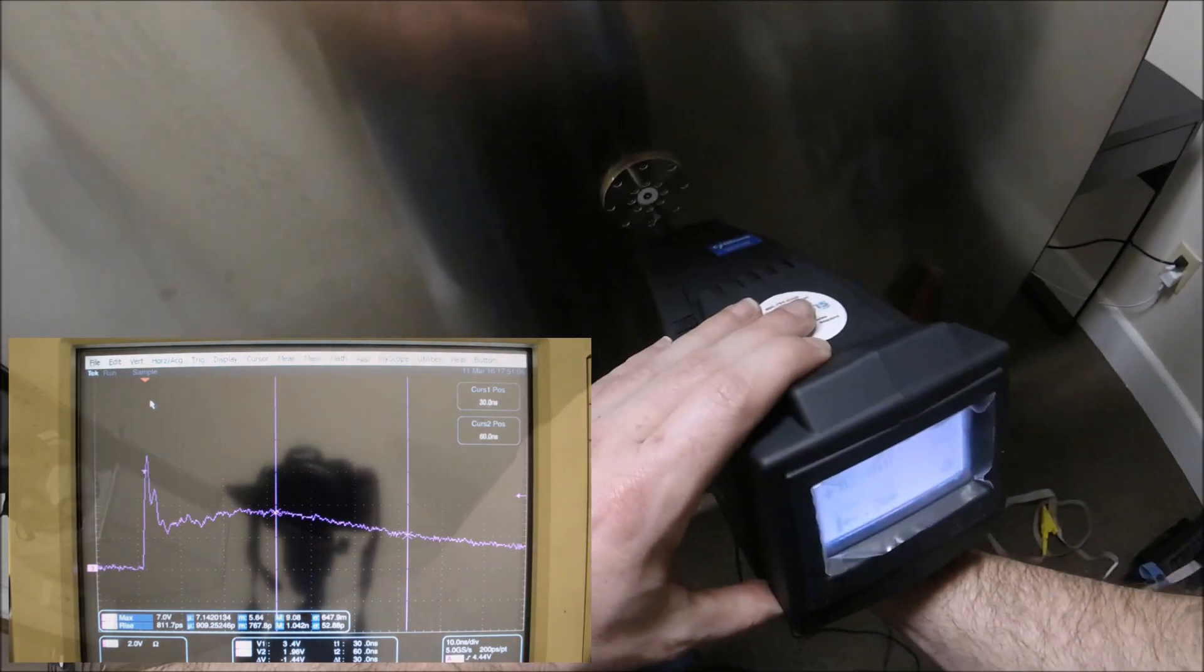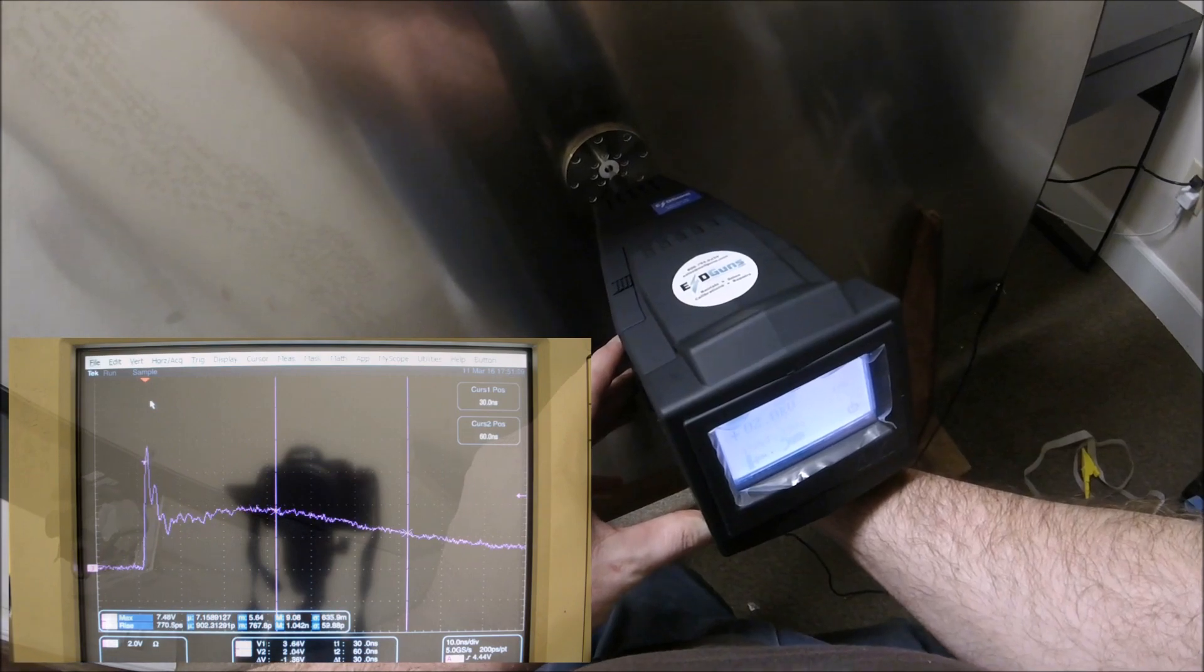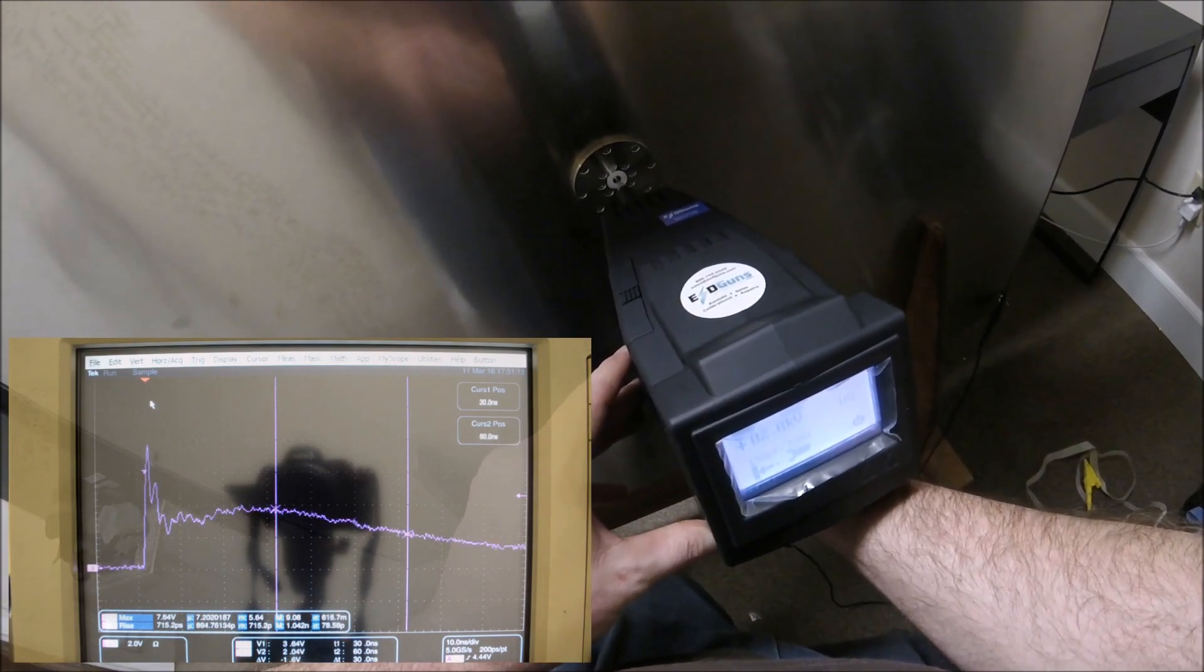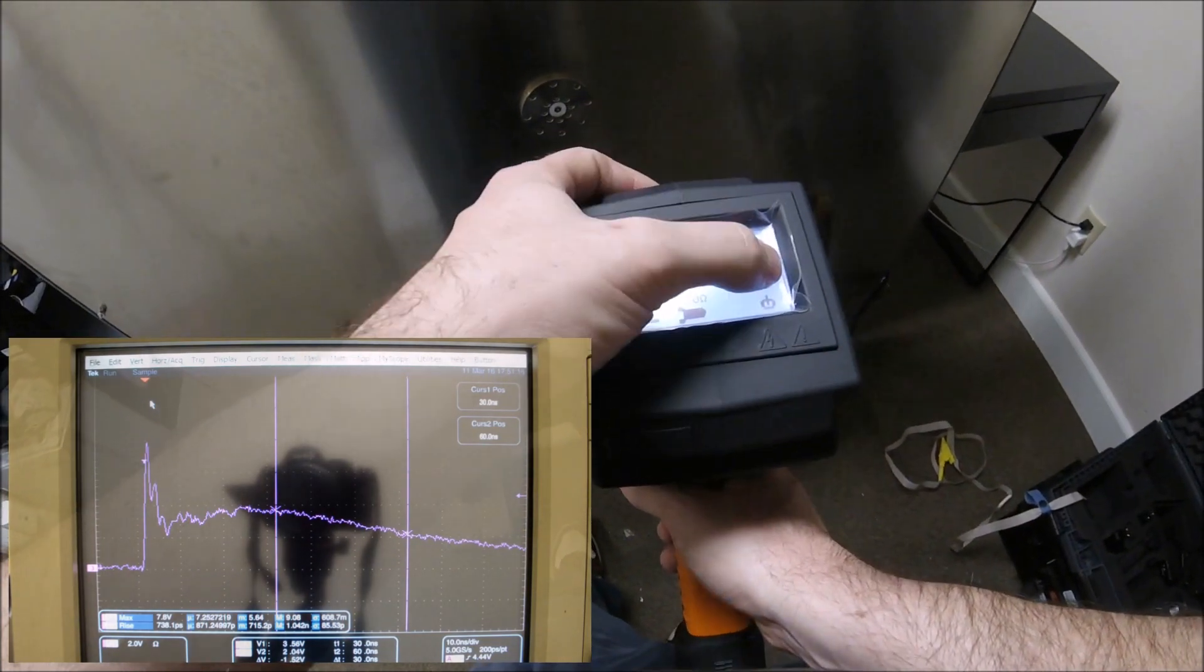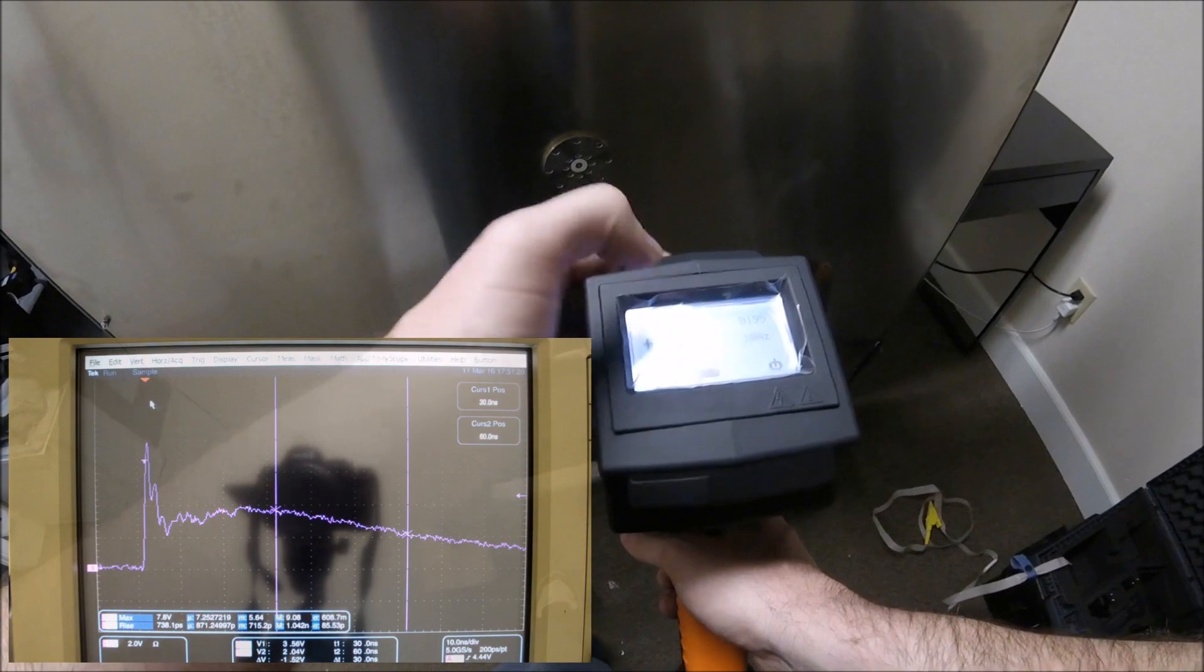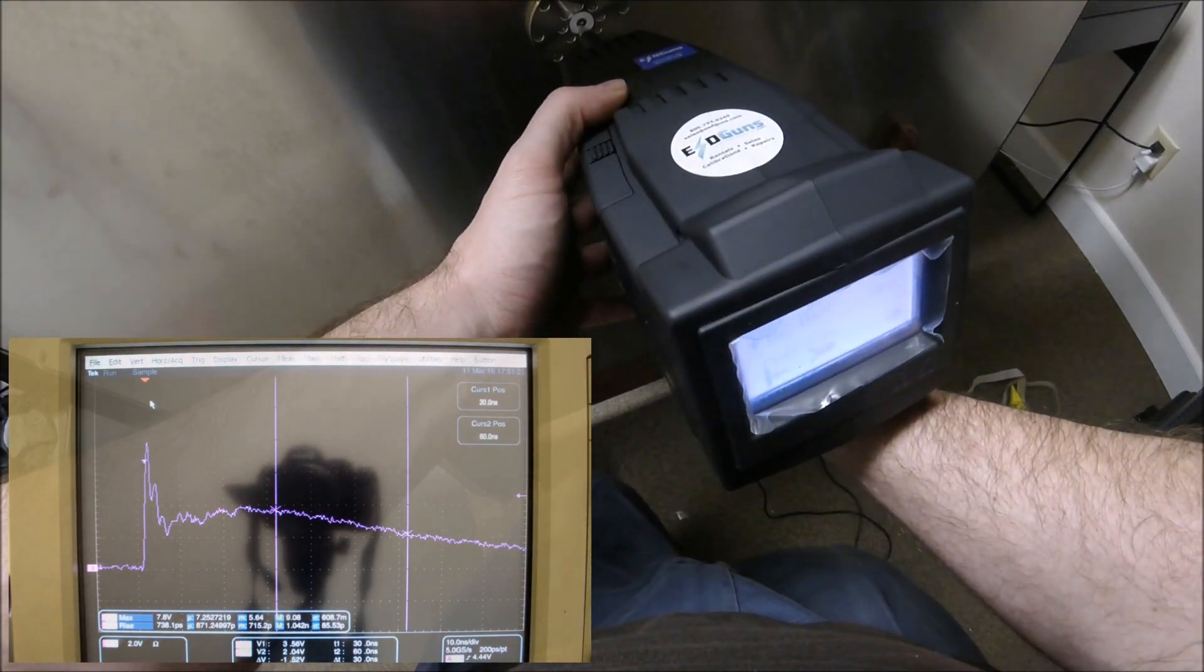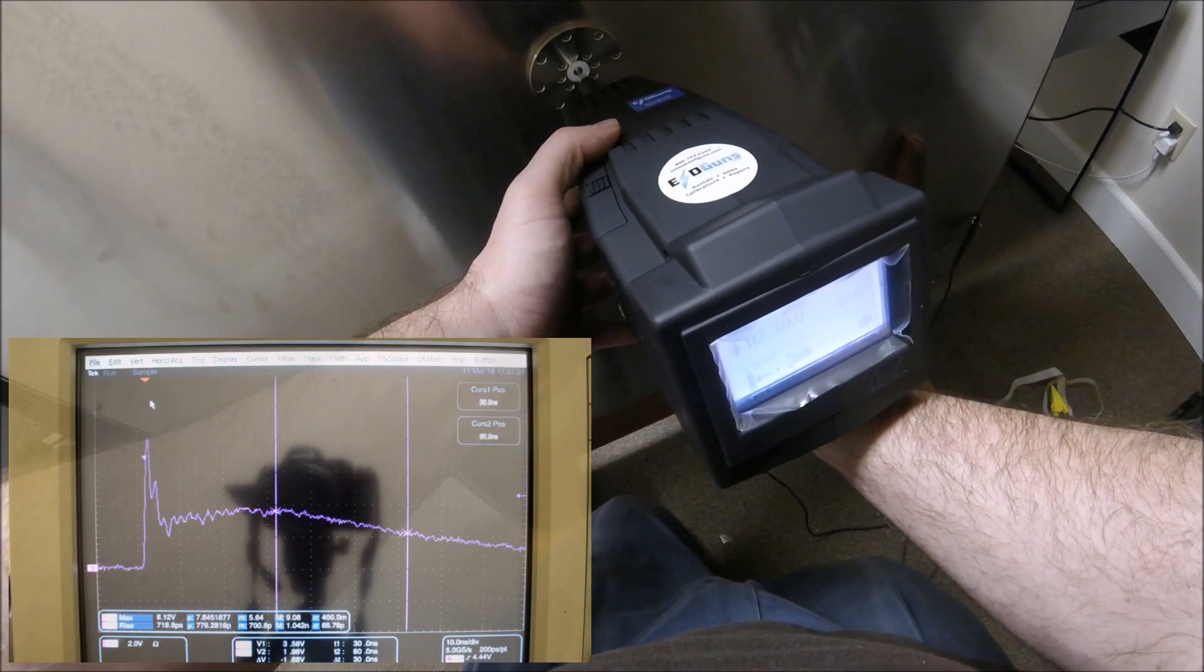The 3C test EDS 20 is the newest unit to the market and it bears physical similarities to the Haefely Onyx. But the waveform and output is comparable to an EM test unit, containing a much more defined secondary peak, but still its own unique waveform. Feel free to jump around the video to do comparisons.